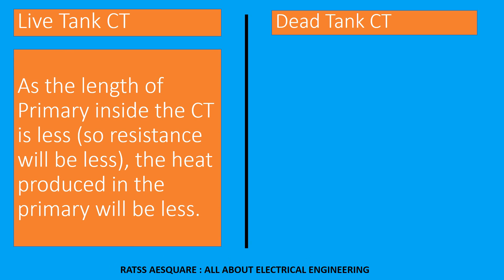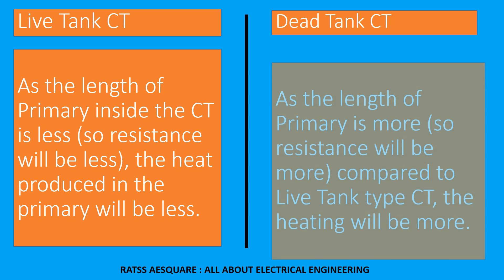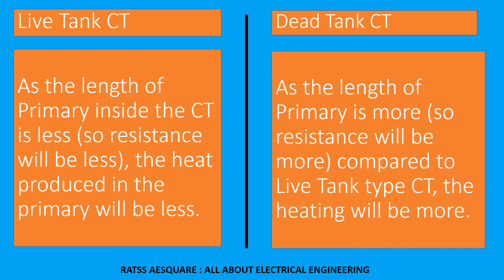In live tank CT, as the length of the primary inside the CT is less, resistance will be less, and the heat produced in the primary will be less. In dead tank CT, as the length of the primary is more, resistance will be more compared to live tank type CT.